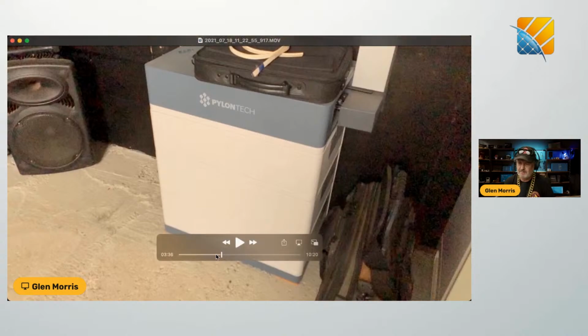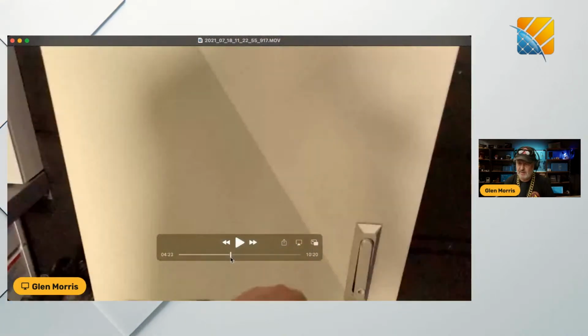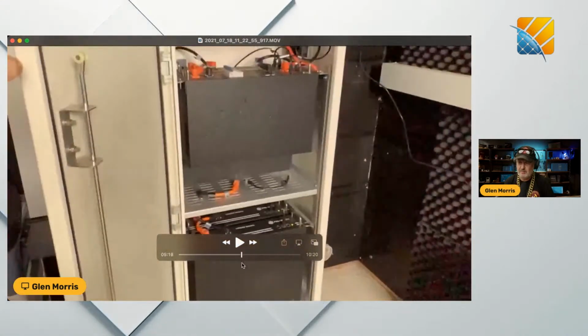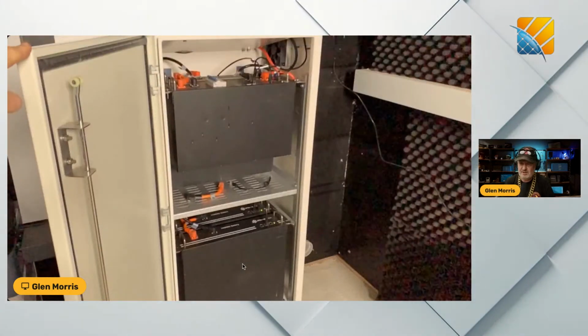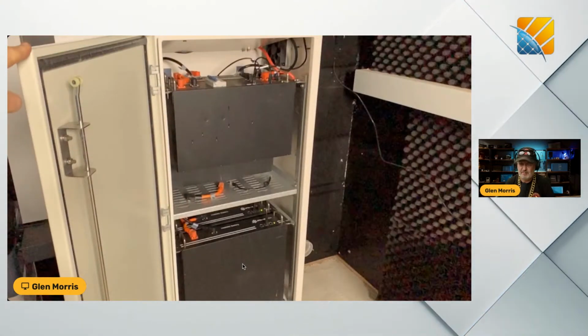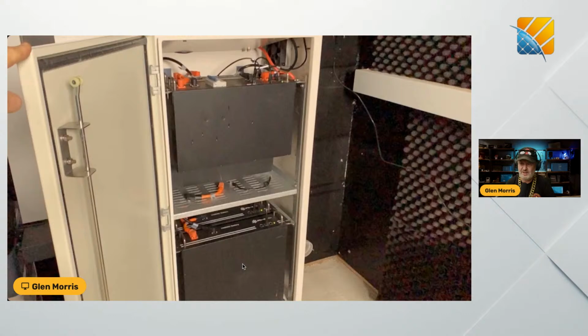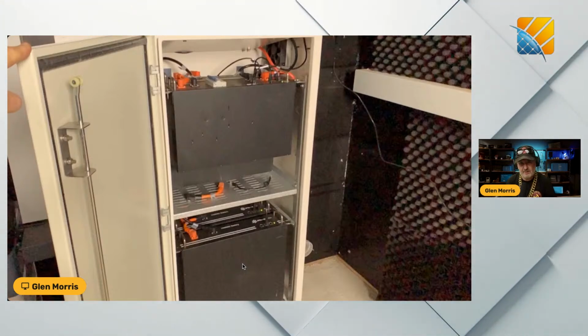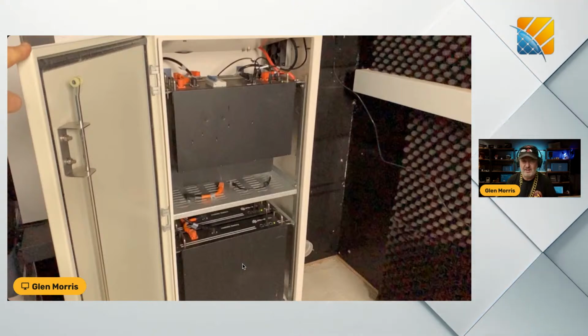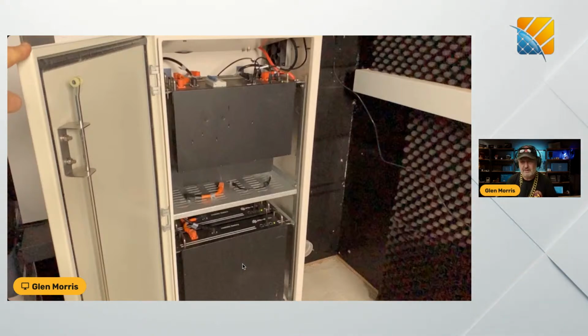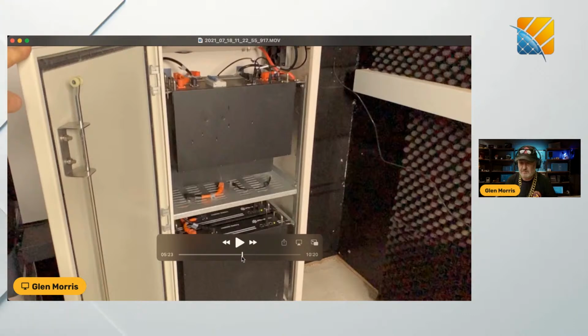That's great for space, but next to it is the rack mount solution. Opening up here, these are 19-inch rack mount style battery modules in a vertical orientation, and you can have up to 6 in that cabinet. We've got 4 battery modules plus the BMS controller, so 4 battery modules each at 50 volts connected together in series, giving a 200 volt battery pack, feeding one of those 2 Ingeteam inverters.